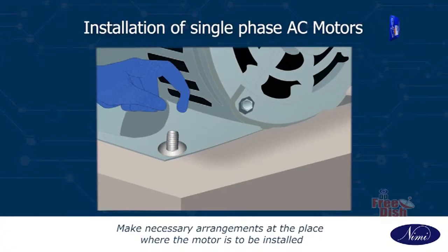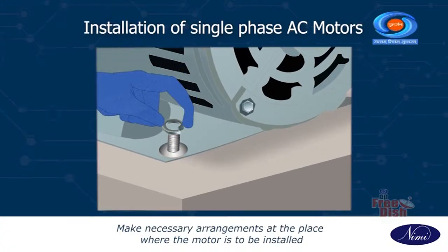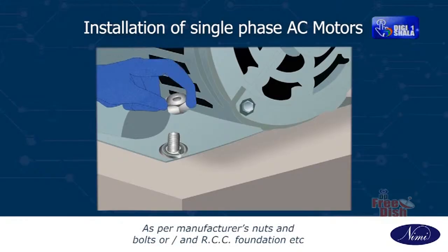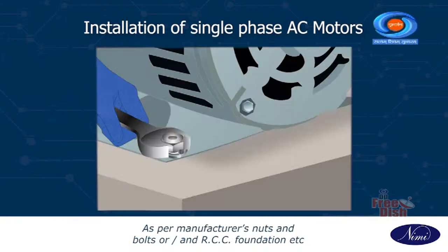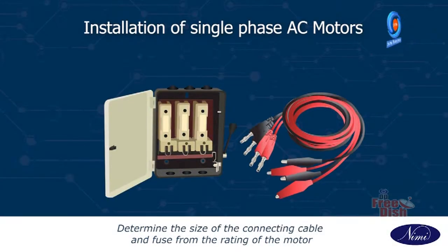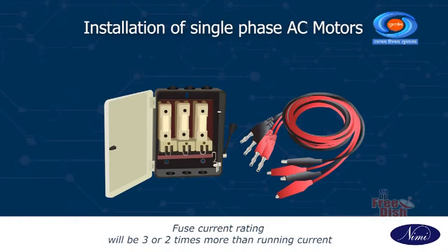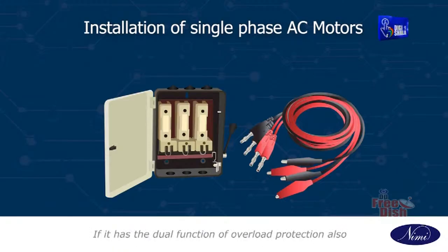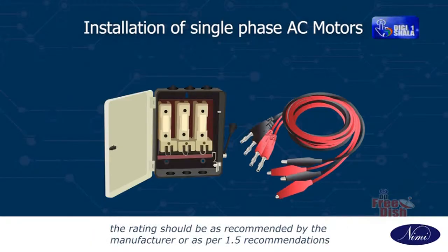Make necessary arrangements at the place where the motor is to be installed as per manufacturer's nuts and bolts or RCC foundation, etc. Determine the size of the connecting cable and fuse from the rating of the motor. Fuse current rating will be 2 or 3 times more than running current. If it has the dual function of overload protection also, the rating should be as recommended by the manufacturer or as per recommendations.